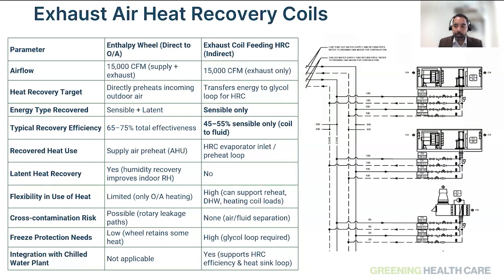you can recover, because eventually frost on the exhaust side coils is a limitation. However, with heat recovery chillers, that limitation is kind of removed, because you're actually not putting anything directly into the outside air. You're putting all that heat back into the heat recovery chiller and then reusing it in the building through hot water loop systems. So that is another thing to consider, and we do have an example today with the Lake Ridge site, which has utilized this concept to further increase the heat recovery chiller load availability on their site.